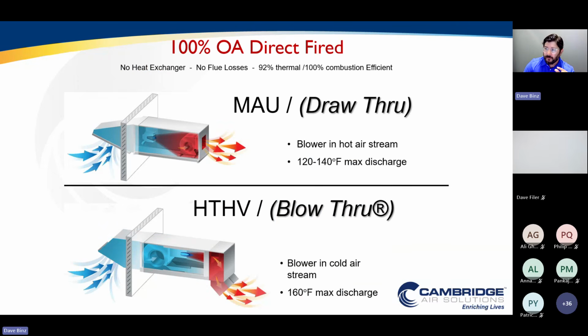Just to make sure we're clear on the differences, because oftentimes we hear these words used synonymously: a makeup air heater, a makeup air unit, an industrial space heater, an HVAC unit. They seem to be used synonymously, but there are some key differences. Makeup air systems are typically draw through, higher volume. Draw through meaning the blower is downstream of the burner. So my motor, my bearings, and my fan are downstream of the hot airstream.